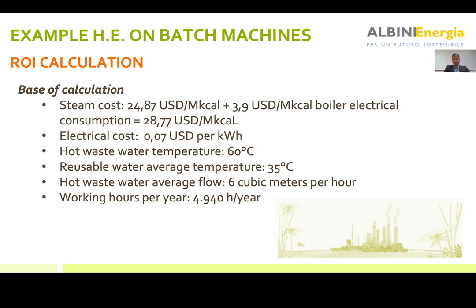The electrical cost we considered in our return on investment calculation was 0.07 US dollars per kilowatt hour. The wastewater temperature was 60 degrees and the reusable water average temperature was 35 degrees. Finally, the flow was around 6 cubic meters per hour.